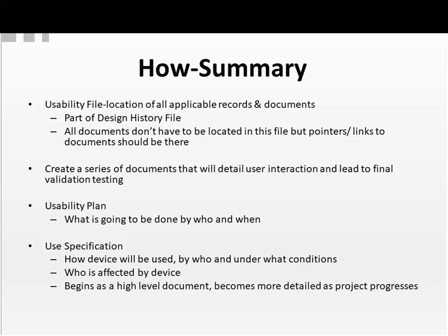Start off with a usability plan, which, like any engineering design plan, is what is going to be done, by who, and when. We then create a use specification for the use of the device.